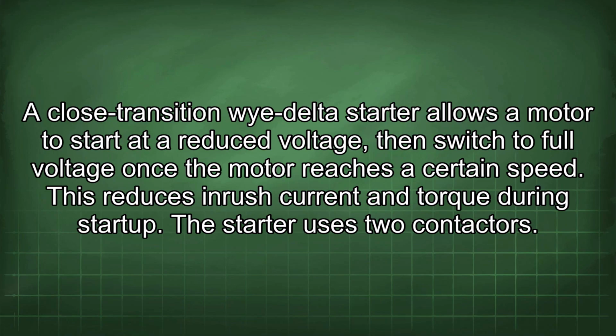A closed transition Wye-Delta starter allows a motor to start at a reduced voltage, then switch to full voltage once the motor reaches a certain speed. This reduces inrush current and torque during startup. The starter uses two contactors.